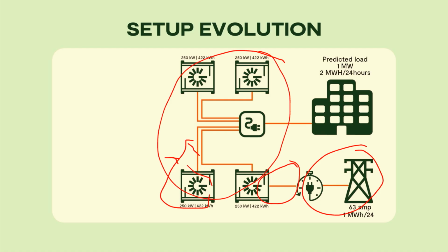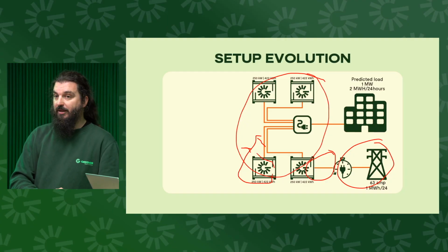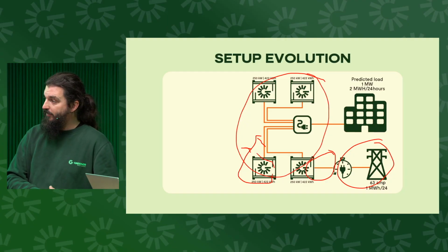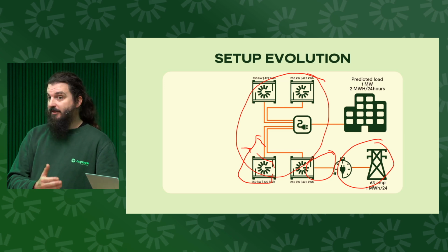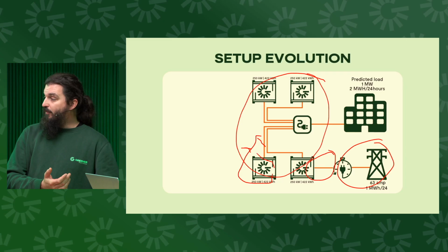Or, if they did their calculations - this was for 1 week, so you're not going to scale up and down - but if you're doing a longer term system, you can scale the data. You can hot scale up and down without having any influence on your process whatsoever. So if you go back to the seasonal thing, if you have no connection or a very small connection, and you're going into the winter season where you have more heating, or going into your high demand period, you can scale up more battery systems for that period with no interruption whatsoever to your power supply.